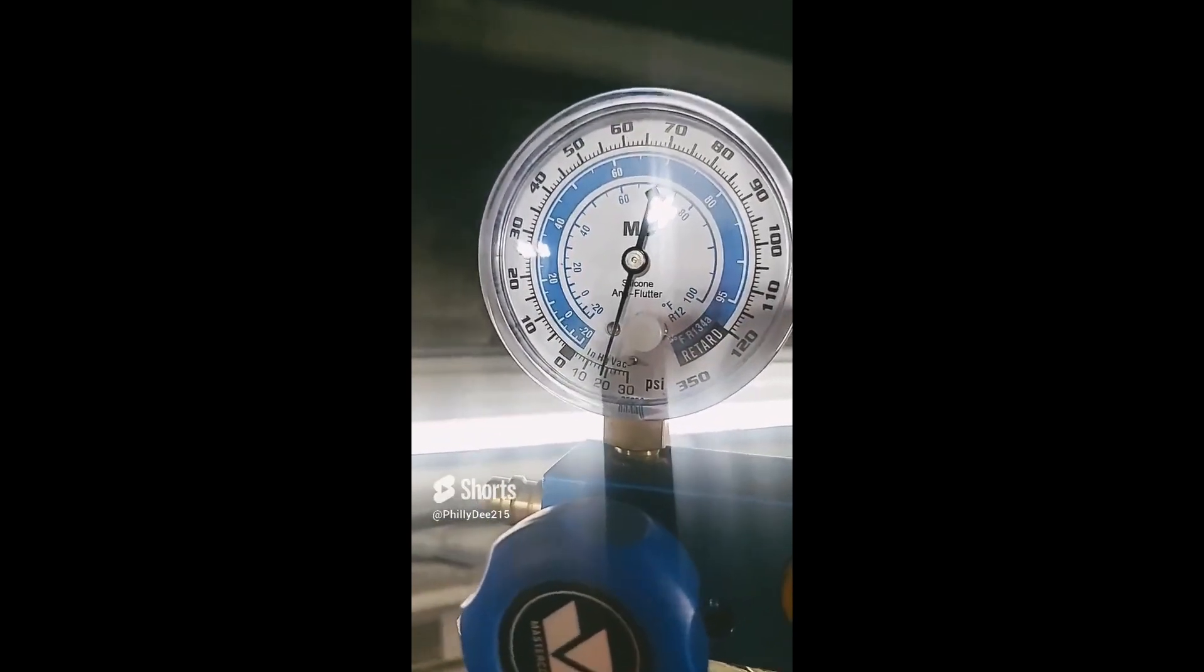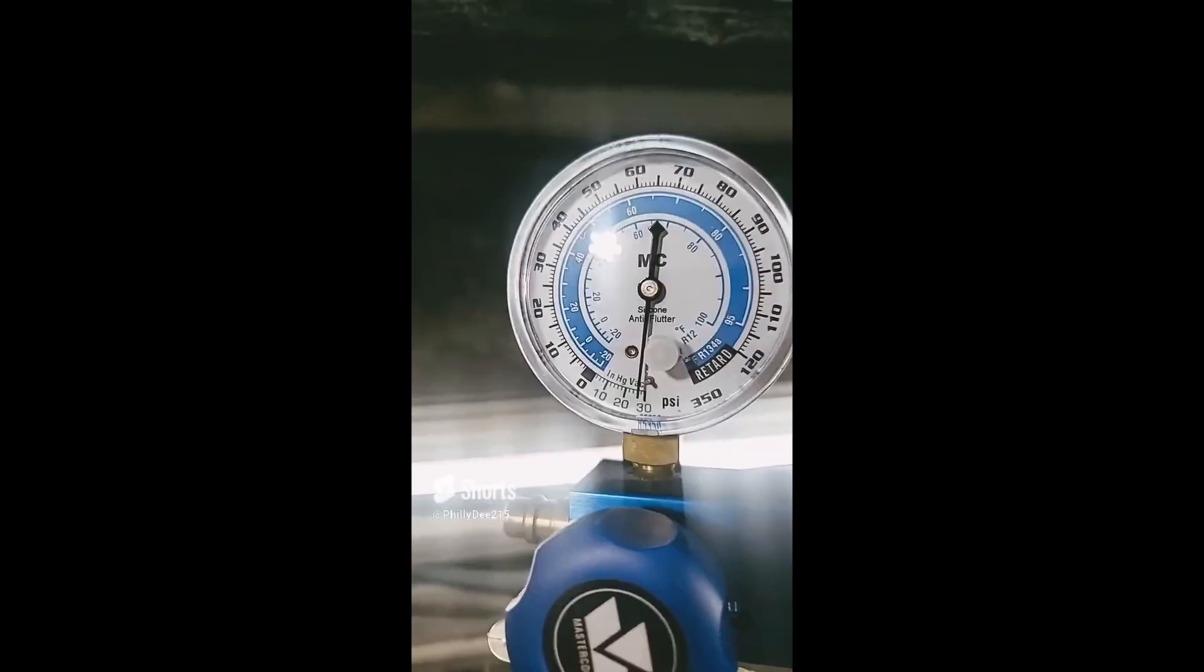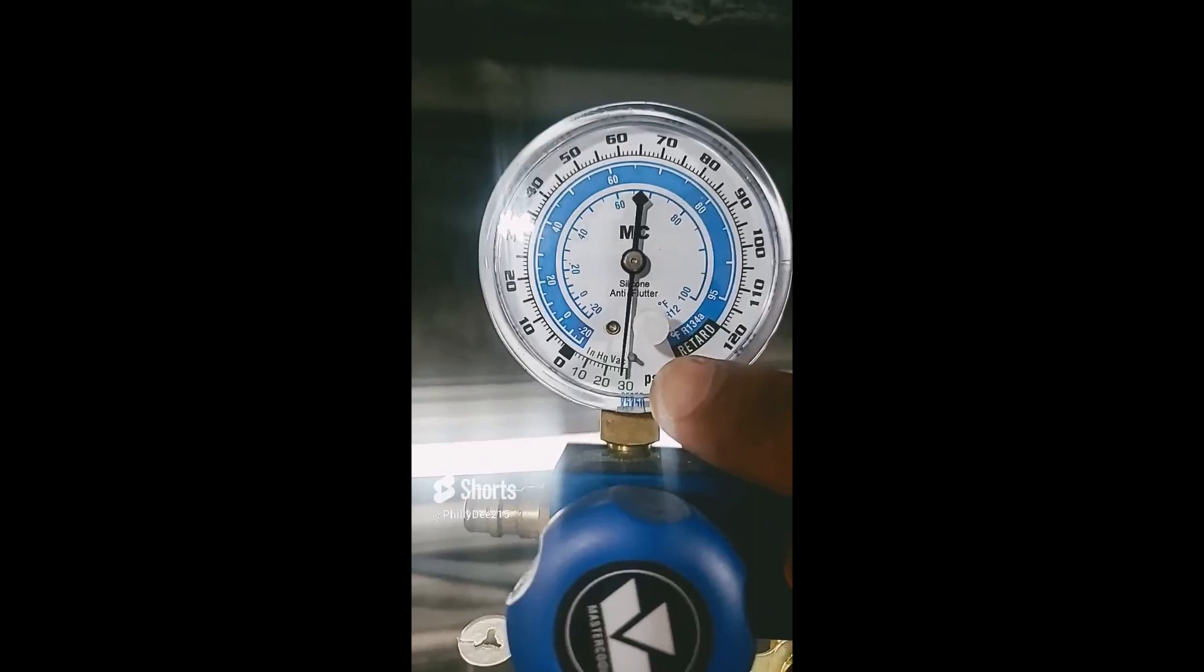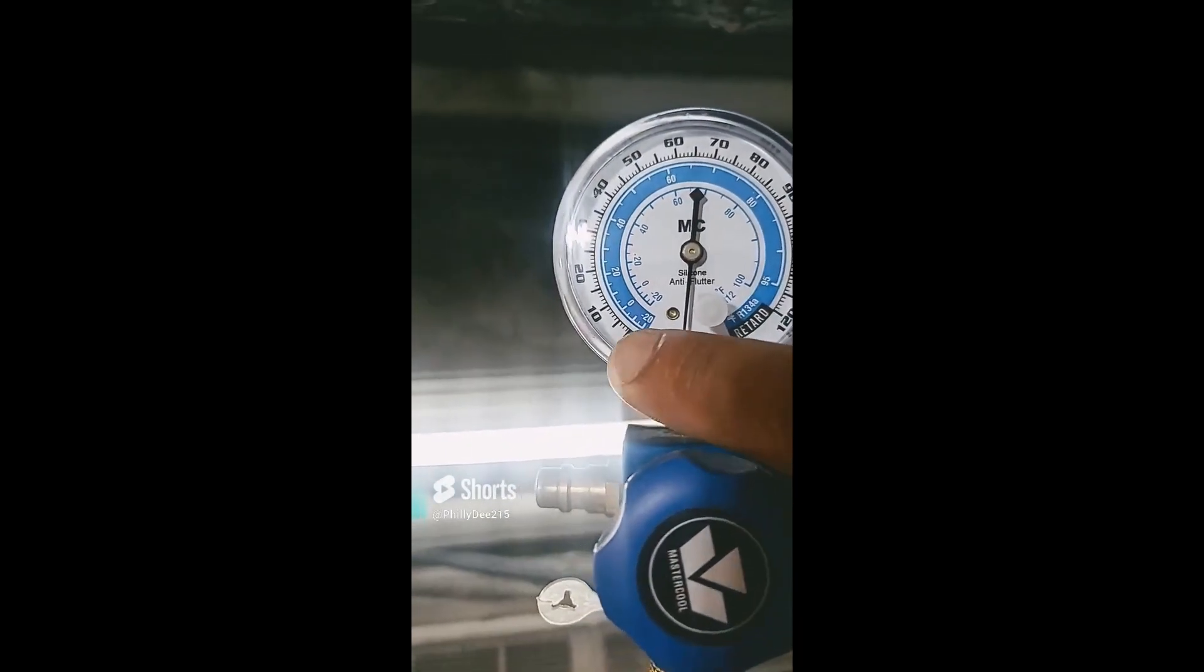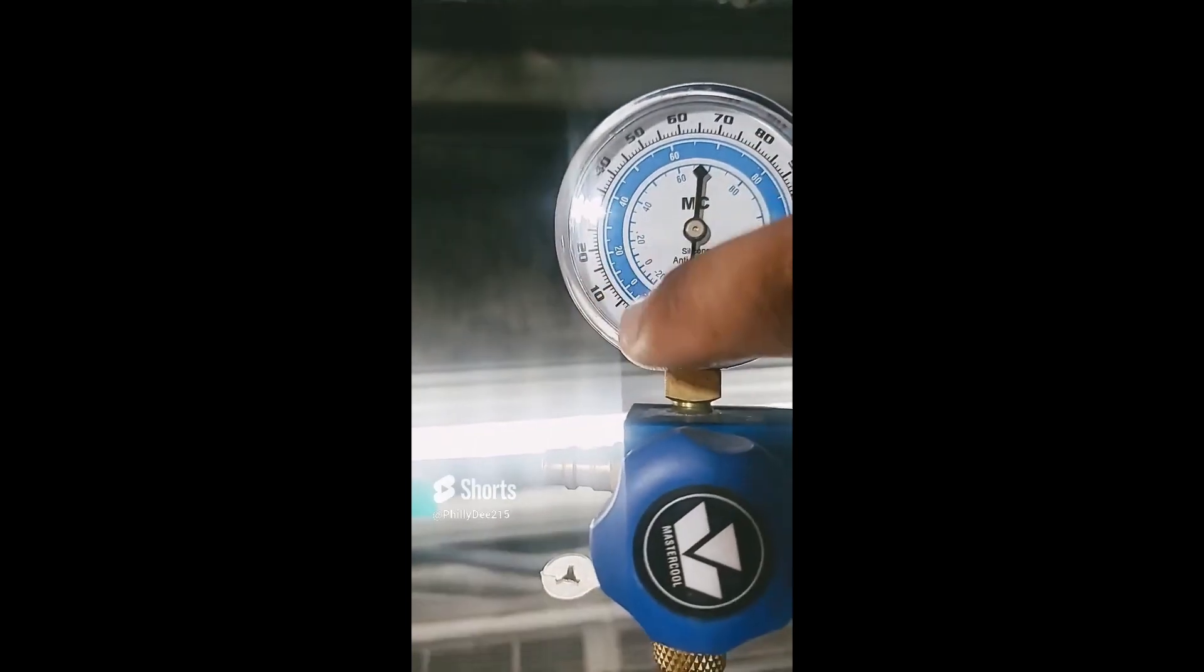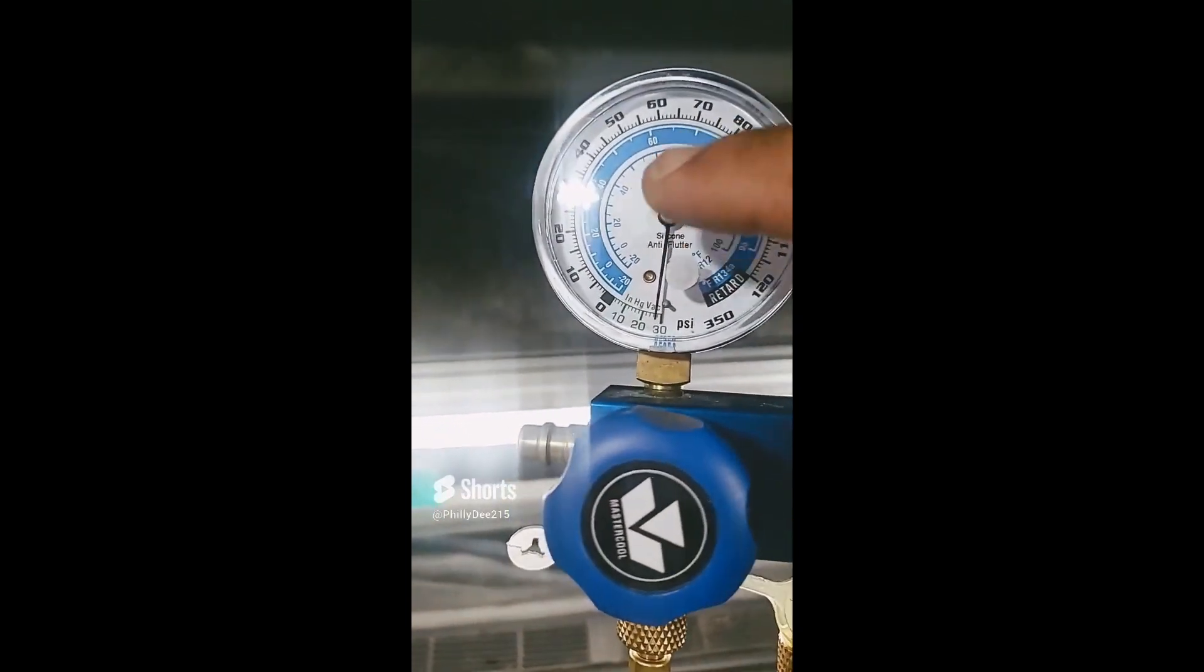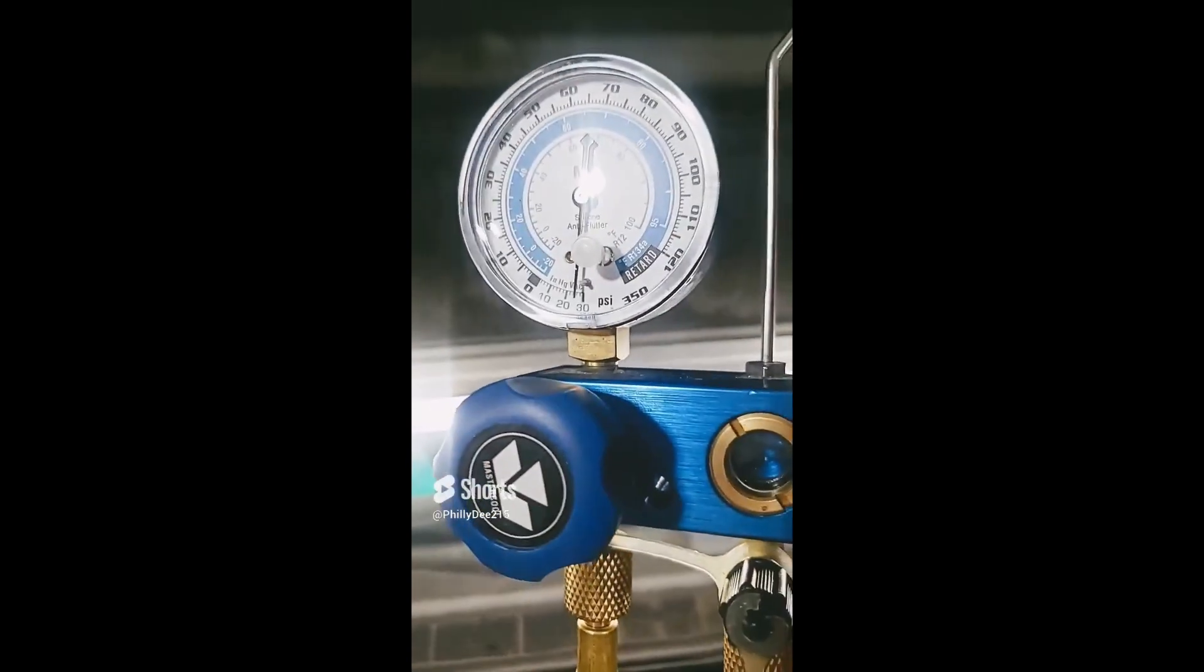Alright. So you want to be anywhere between 28 and 30 inches of mercury. Now, if you have a leak in your system, your gauge is not going to read 28 to 30 inches of mercury. Your gauge is going to stay up here. Okay? Around here. Because if you have a leak in your system, the pump can't pull a vacuum on the system. So don't get that confused.